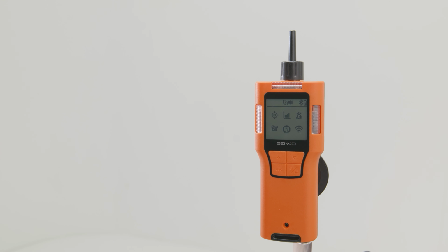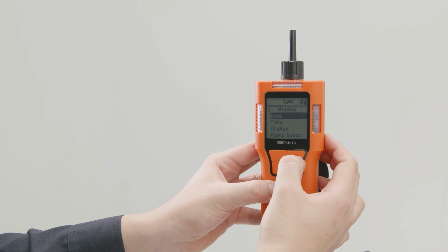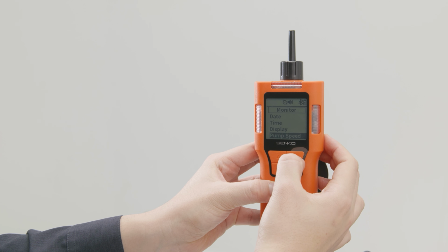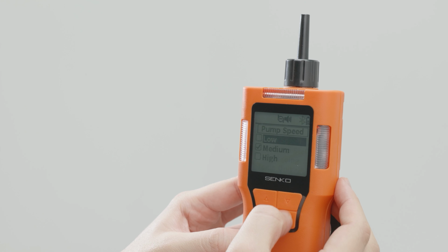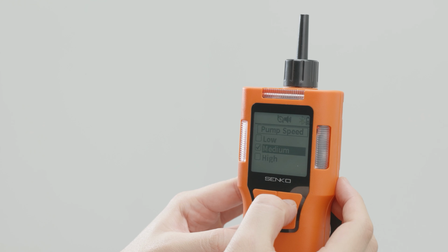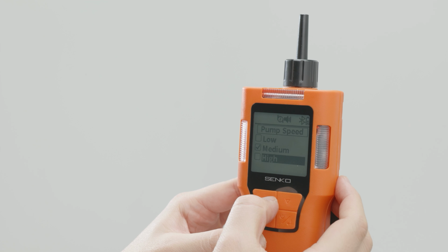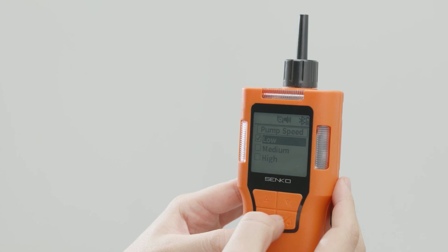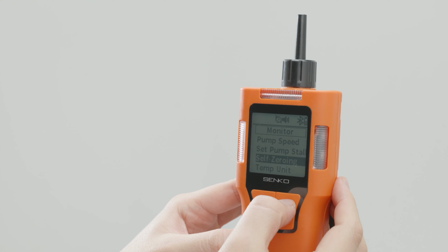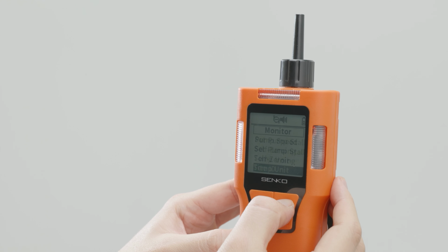In the Monitoring Settings menu, you can set the following items. First, through Date and Time, you can set the date and time of the device. In the display settings, users can adjust the LCD screen contrast and backlight to optimize screen brightness according to the working environment, improving overall readability. Under pump speed, the pump speed can be selected as high, medium, or low. There is approximately a 20% difference in operating intensity between the high and low settings, allowing users to balance sampling performance and power consumption based on site conditions. The Set Pump Stall option allows adjustment of the pump blockage detection sensitivity.